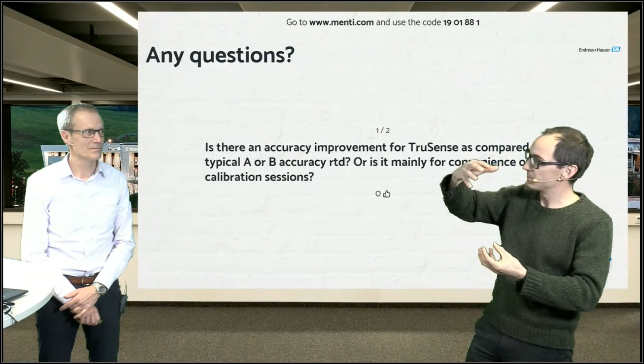When we speak about accuracies, I would like to look at the complete system. Because if you only reduce your view on the sensor, is it a class A, is it a class AA, how accurate is the sensor? This is just one piece of the puzzle. You always have to look at the complete measurement point. So where do you connect the PT100? Normally you go into a standard temperature transmitter, a 4 to 20 milliampere transmitter or a HART transmitter or whatever. So you have a signal change here from analog to digital signal in the transmitter, and you have to take this into consideration as well.